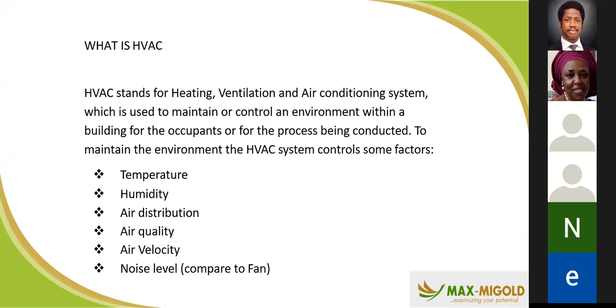If you put it at 18, the temperature of the space might not necessarily be 18. Please don't mistake that, because that has caused trouble in some facilities. Setting the AC to 18 does not guarantee the temperature of the space will be 18 - you're only telling the AC to get the temperature of that space to 18. So if you set up a different measuring device somewhere, if this one is giving you 18, there's a tendency the other one will be giving you 20. The AC is still doing its work until it finally gets it to 18. So don't mix that up, because some of your clients might call you asking why the thermostat shows 18 and the place is so hot.